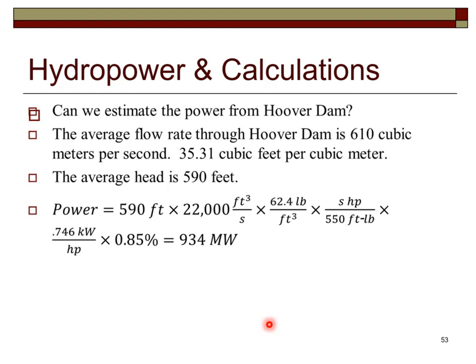To estimate the power of Hoover Dam: the average flow rate is 610 cubic meters per second (approximately 22,000 cubic feet per second) and the average head is 590 feet. Multiplying 590 ft × 22,000 ft³/s × 62.4 lb/ft³, dividing by 550 ft·lb/s per horsepower, multiplying by 0.746 kW per horsepower, and applying 85% efficiency gives approximately 934 megawatts.